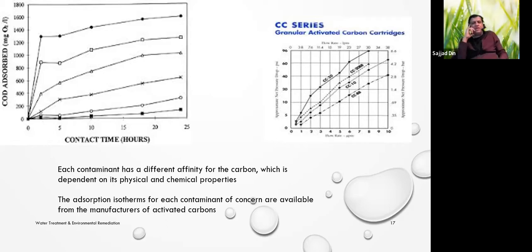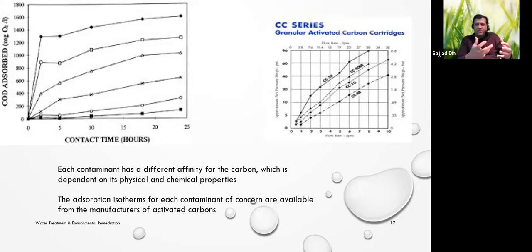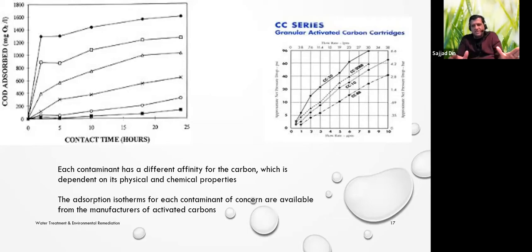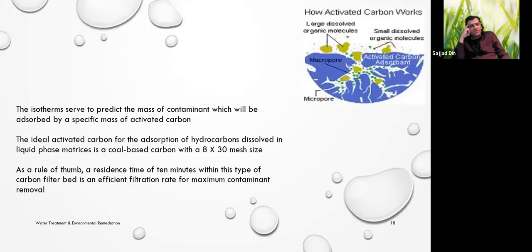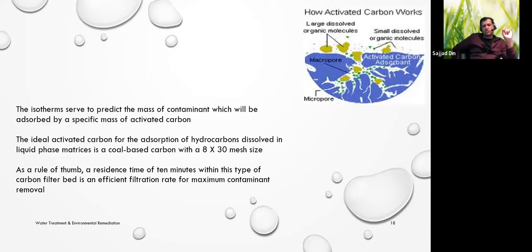Granular activated carbon is basically like roasted coconut shells — a very adsorptive material with many nooks and crannies and high porosity, so organic compounds love to stick to it. It looks like a little black powder. As water flows through it, it strips contaminants. The ideal activated carbon has a mesh size of about 8 by 30 mesh, and the residence time you're looking for is about 10 minutes for maximum performance.